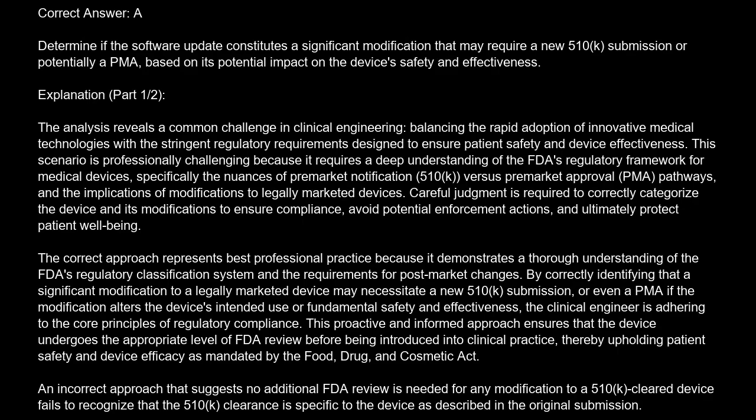The correct answer is A. Determine if the software update constitutes a significant modification that may require a new 510K submission or potentially a PMA based on its potential impact on the device's safety and effectiveness. Explanation. The analysis reveals a common challenge in clinical engineering, balancing the rapid adoption of innovative medical technologies with the stringent regulatory requirements designed to ensure patient safety and device effectiveness.